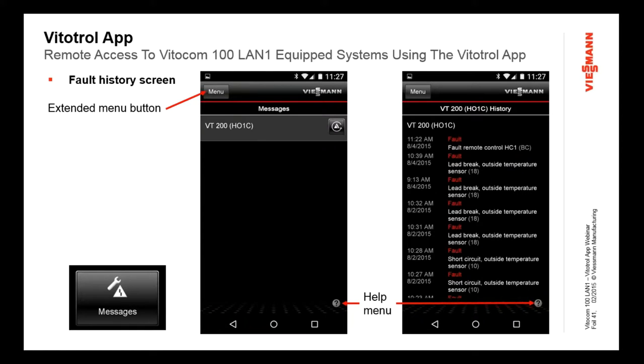Then under the messages, I see over here I have the control. So if I had more than one boiler control, like three boilers in a cascade, they'd all be listed here, and you would simply click on this to get it. But in this case, we only have one. So when I click on the alarm button, I'm going to see all of the faults that have happened in that control since the last time it was reset. Just like the message you get in the email, it's going to tell you a timestamp, tell you that it's a fault, and that there's a fault in that controller. You can see here it says lead and outdoor temperature sensor, so it gives you some information, with fault code 18 beside it. That's the information you'll get.